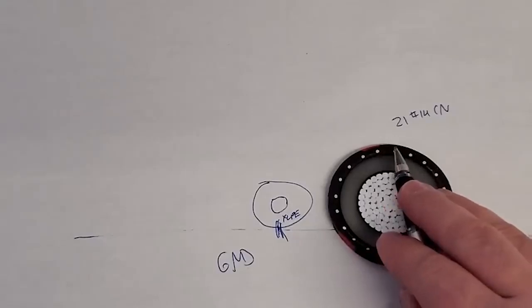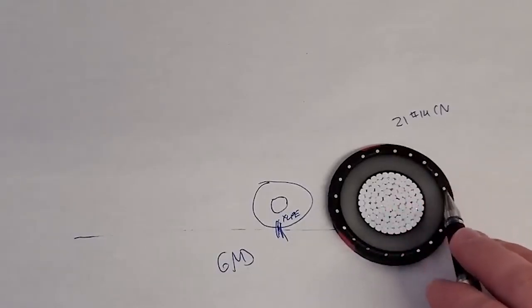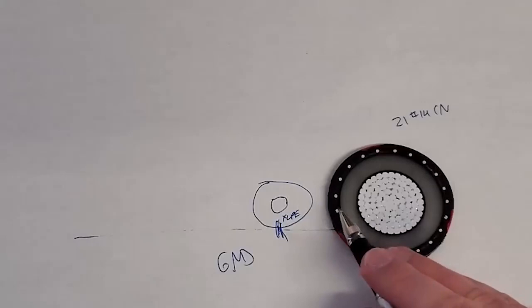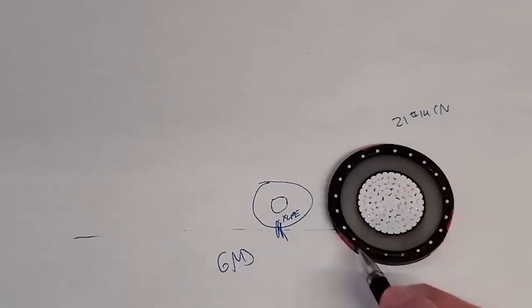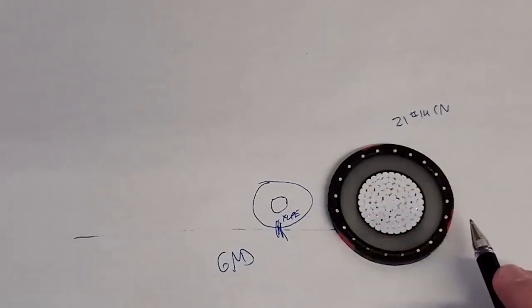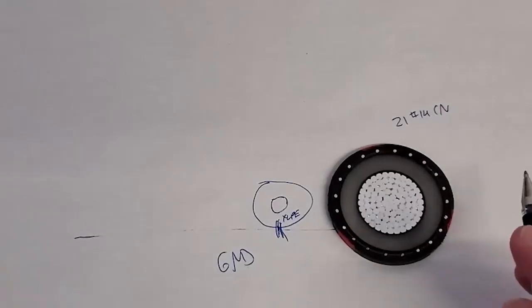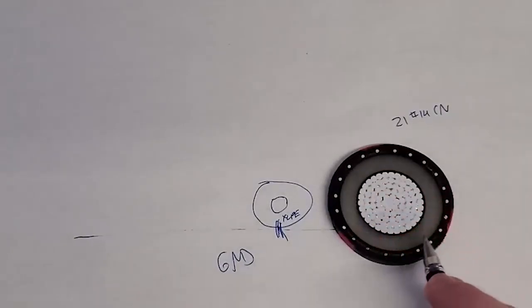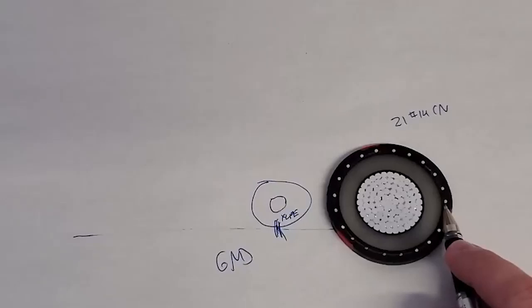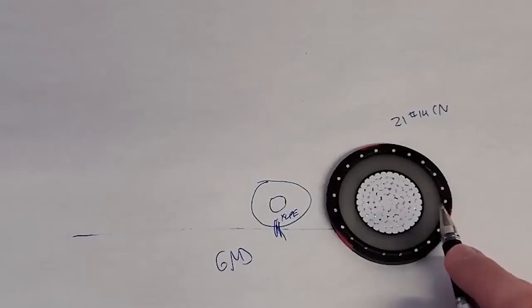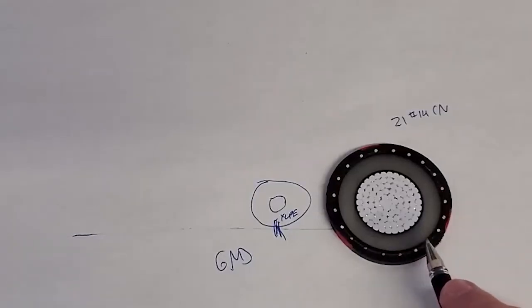21 of number 14 gauge copper conductors. That's it. What determines the size of this? The fault current decides the size of that. So if you have, say, just one example, a much larger main power transformer that has a higher fault current, you're going to see a lot more of these concentric neutrals, and the size is probably going to be bigger. It might be a number 12 or number 10. There could be 30 of them. So what determines that is the fault current.